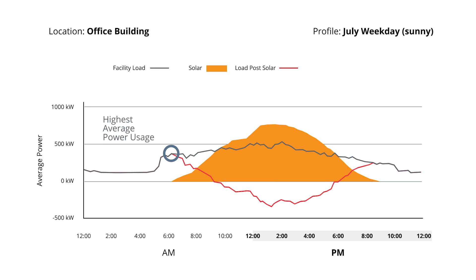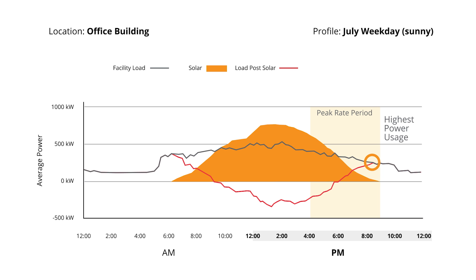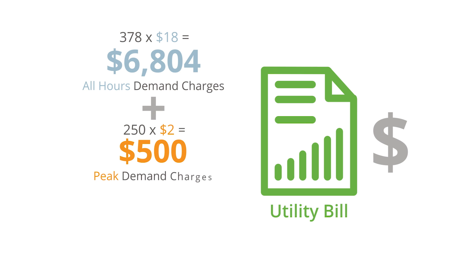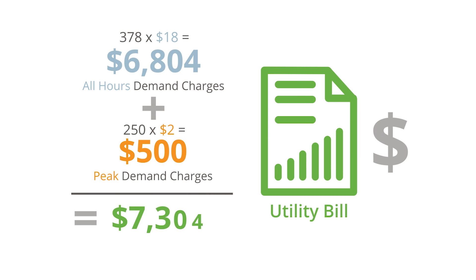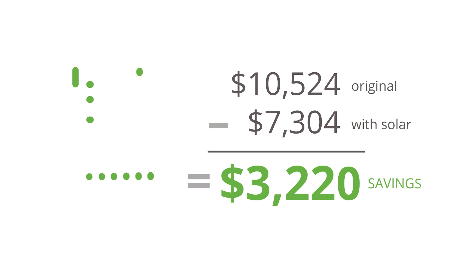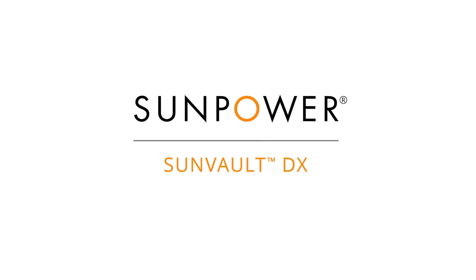The new highest power usage for all hours of the day now happens around 6:30 in the morning and is 378 kilowatts. The highest power usage during the peak time of use period occurs around 8:30 p.m. and is 250 kilowatts. When we do the math based on the previously stated demand charge rates, they now add up to a little over $7,300 this month, which represents about $3,200 in demand charge savings with solar installed. Which is great, but our Sunvault DX storage solution can save you even more.